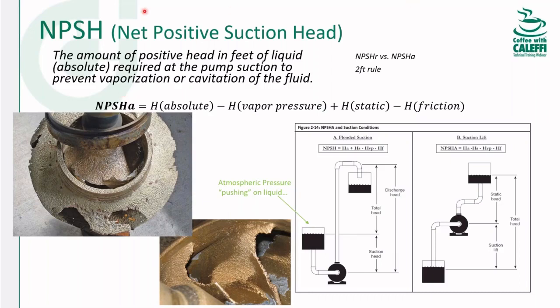But the equation, your net positive suction head available, you'll see that's a system thing, how much NPSH do you have available. And on the pump curves, it says NPSHr, which is for required. So your available is your absolute pressure. This is atmospheric pressure at whatever elevation you're at, and then you subtract the vapor pressure of the water. So ambient temperature water has a low vapor pressure, but when you're doing boiler feed at 200 plus degrees, the vapor pressure pretty much cancels out with the atmospheric pressure. And then if you have any static head above the inlet of the pump, you can add that, but then you subtract the friction. And so on the little diagrams, on the left side, we've got a flooded suction where there's a tank feeding the pump. So you got the atmospheric pressure pushing on the liquid.